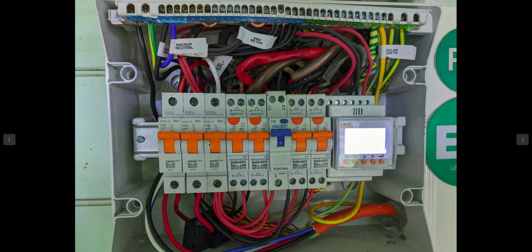Yeah, here I don't have the 2-pole switch. And the inspector wanted it like that, not me. He said, oh, you've got to be able to switch them separately, blah, blah, blah, whatever. Okay, so this one has a main switch here, grid side and off-grid side. I like to use a multi-core cable. As you can see, it's 3-phase multi-core, 3-phase, neutral and earth, because then I can colour code. See, backup neutral's blue. Black is grid neutral, because in Australia black is generally neutral. Red is generally active, 1-phase supply, so that becomes the grid side, and the white becomes the off-grid colour. I like to use multi-core, very, very simple.